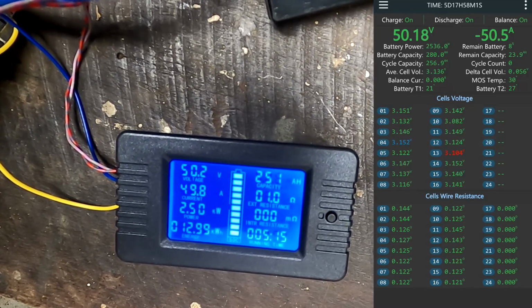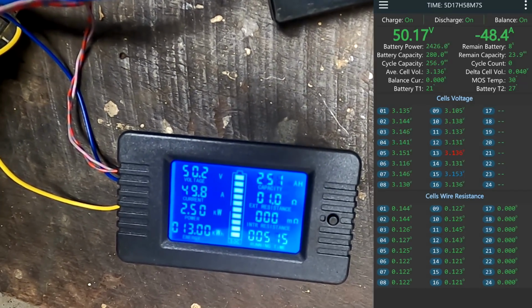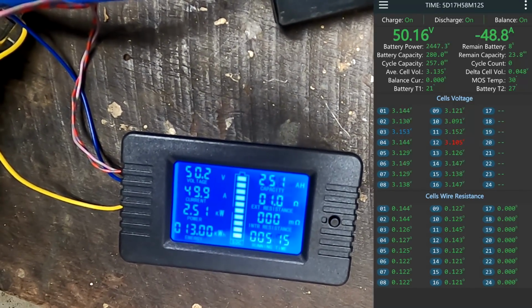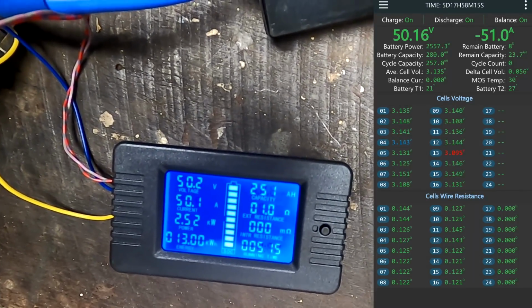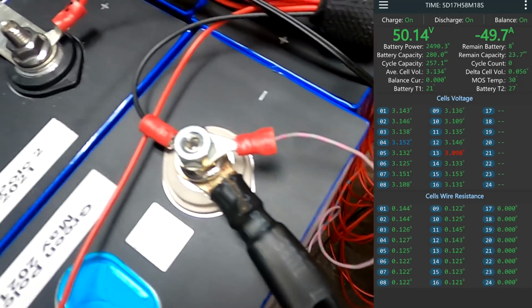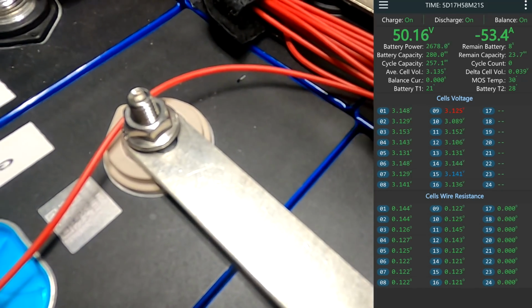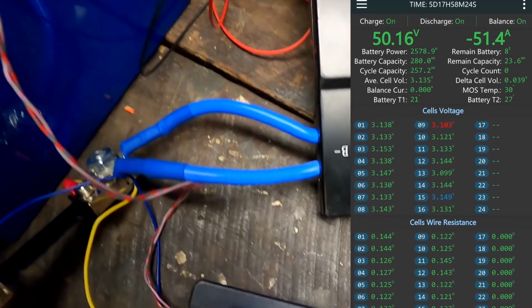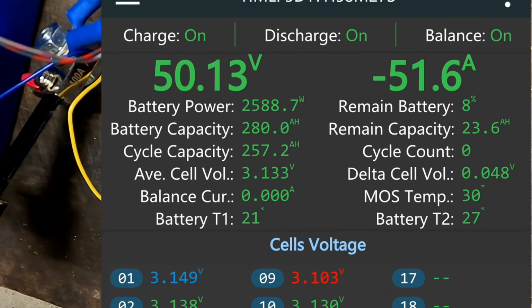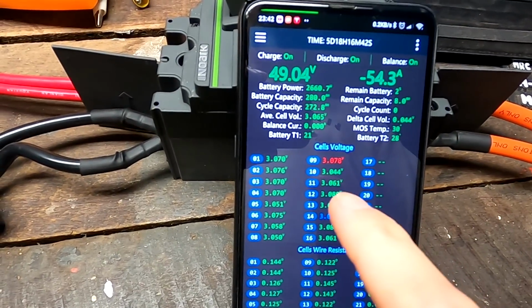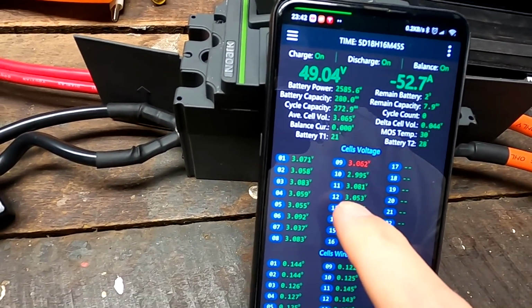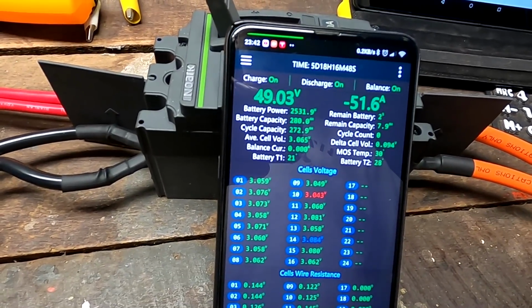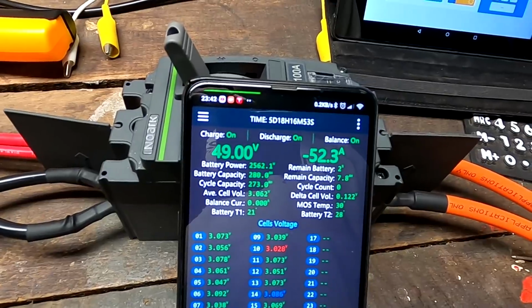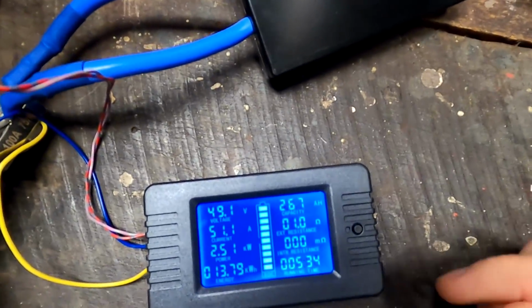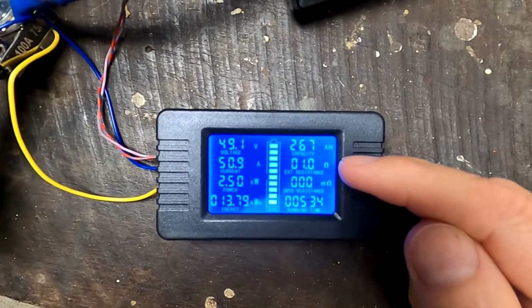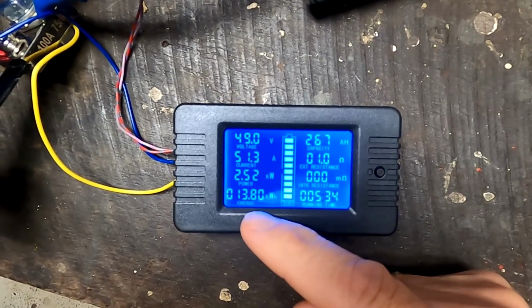We are still at 3.13 volt average cell voltage. There, 40 millivolt deviation. I could also sneak the battery temperature sensor number 2 into our battery pack here. Here it is. And here was a gap, and I could push it really down so we can see the temperature of the battery pack now as well. 27 degrees. Oh, we're having the first cells showing 2.999. We've got 2% left, 7.8 ampere hours. And here the power meter says we've discharged 26.7 ampere hours, 13.8 kilowatt hours so far.